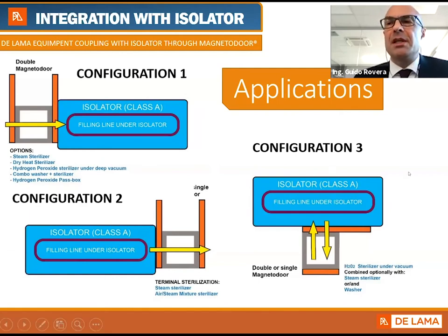Configuration number three is instead when the Lama equipment is used as an ancillary equipment to the isolator. For instance, as an example, you have your filling line within the isolator. You want to wash and sterilize the machine parts which are needed for the change format, and you load them inside the Lama equipment, and re-download them into the isolator at the end of the very process.